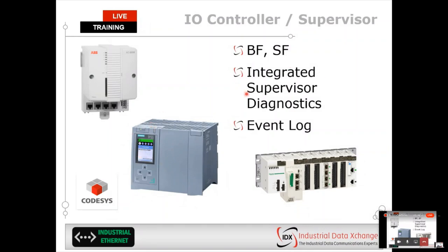Understand how to use supervisor diagnostics, whether you get training from these manufacturers, or attend certified PROFINET training with IDX Academy. We go into these internal diagnostic logs and show you different common errors. A lot of these controllers will have an event log as well, which indicates the snapshot in time of what occurred and why the device disconnected. It gives you more clues and hints on where you can identify a fault on that network.